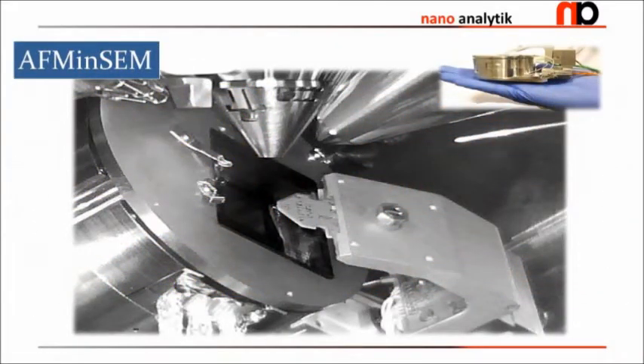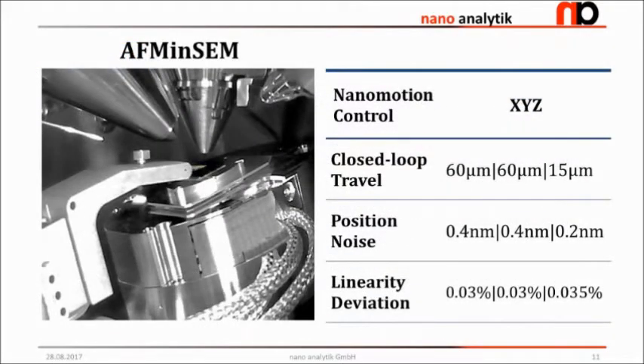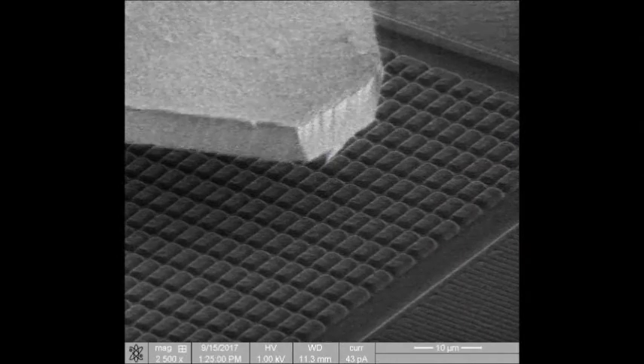Image of the AFM in SEM taken with the infrared camera of the SEM/FIB tool, where the AFM is tilted at 60 degrees relative to the SEM column. To create the tool, a sample scanner that provided metrological capabilities was used. It was initially calibrated and tested by the manufacturer. The following are the performance criteria.